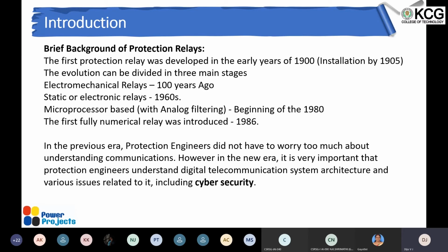But just to give an understanding, in the previous era the protection engineers did not have to worry too much about understanding communication, because such an issue was not there. I mean communication with respect to the relaying point, not in general. The communication to the relay, or taking any values from the relay, was not there. And in the new era, it's becoming a very important aspect for protection engineers to understand the digital communication system architecture and various issues related to it, including cybersecurity. So nowadays all protection engineers need to have some understanding of communication.